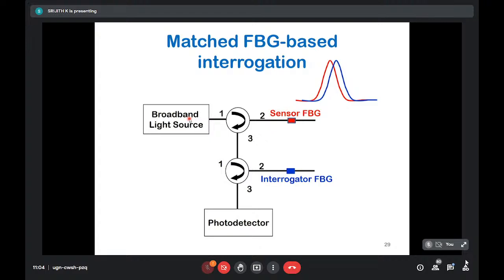So then you have another technique where you use both a broadband light source and a photodetector. However, you need two FBGs for this. So you have a sensor FBG and an interrogator FBG. The amount of intensity that is fed into the photodetector will depend on the overlap between these two FBGs. You deliberately make the sensor FBG and interrogator FBG slightly different in Bragg wavelength, so that you have an overlap, which you see here. This is the overlap, and that overlap is what is going to be read by the photodetector.